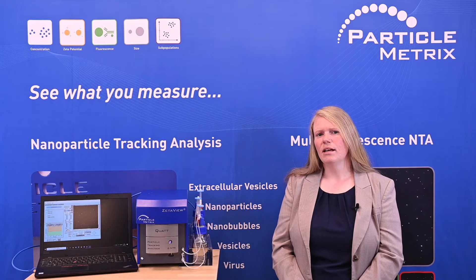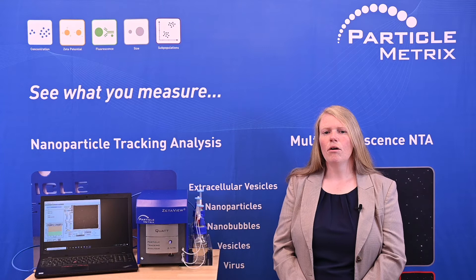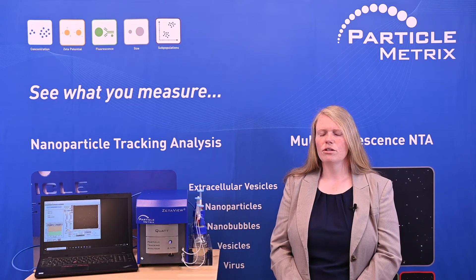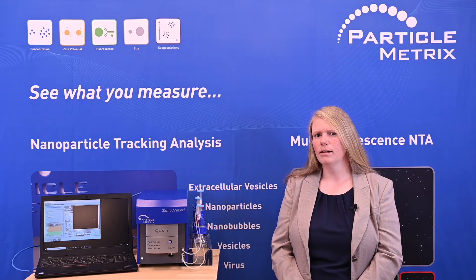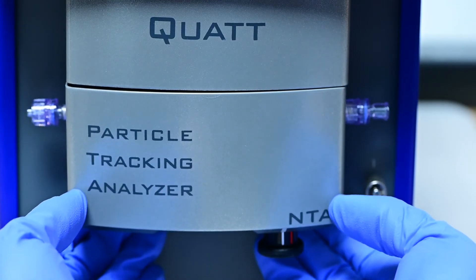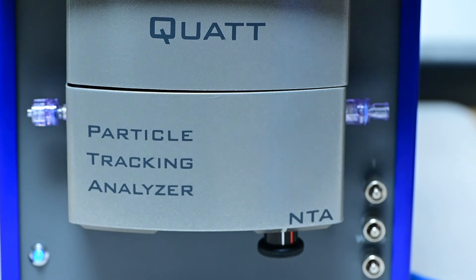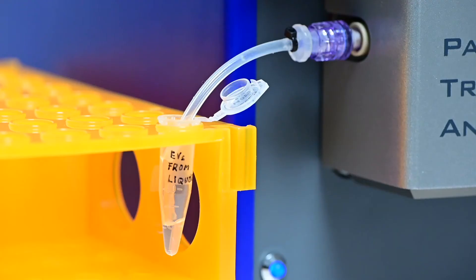To deal with low sample volume and low vesicle concentration, the ZetaView can already work with a concentration of only 10 to the power of 5 particles per mL. In case you want to recover your sample after measurement, no problem — we can equip your system with a measurement cell which makes recovering easy without mixing with any kind of buffer.